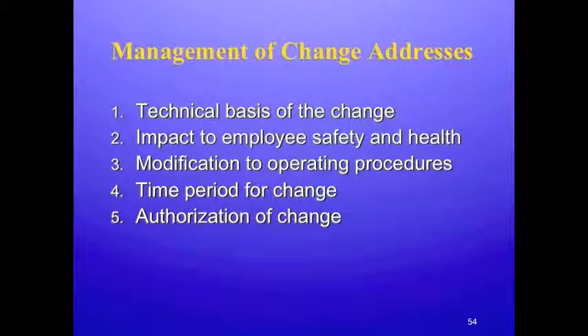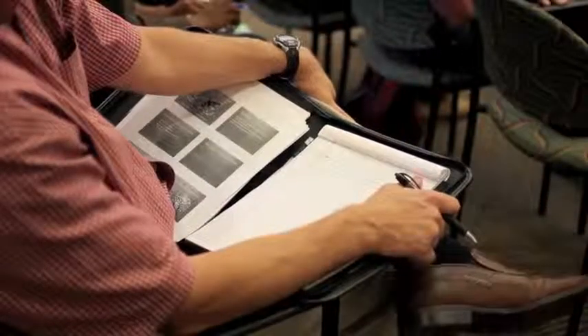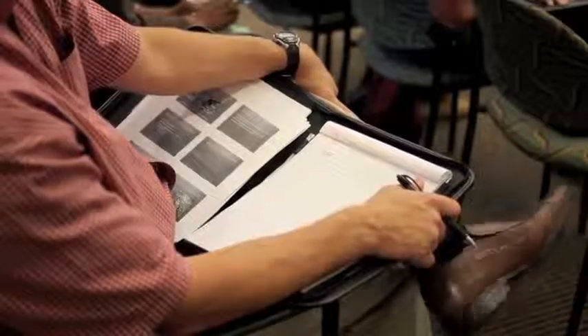Employees who operate a process and maintenance contract employees whose job tasks will be affected by a change in the process must be informed of and trained in the change prior to startup of the process or startup of the affected part of the process. If a change covered by these procedures results in a change in the required safety information systems, such information must also be updated accordingly. If a change covered by these procedures changes the required operating procedures or practices, they must also be updated.